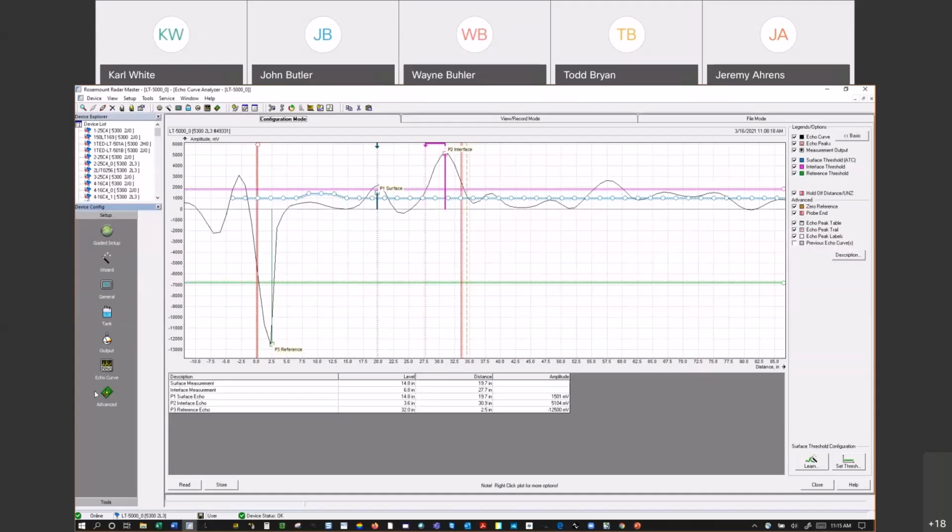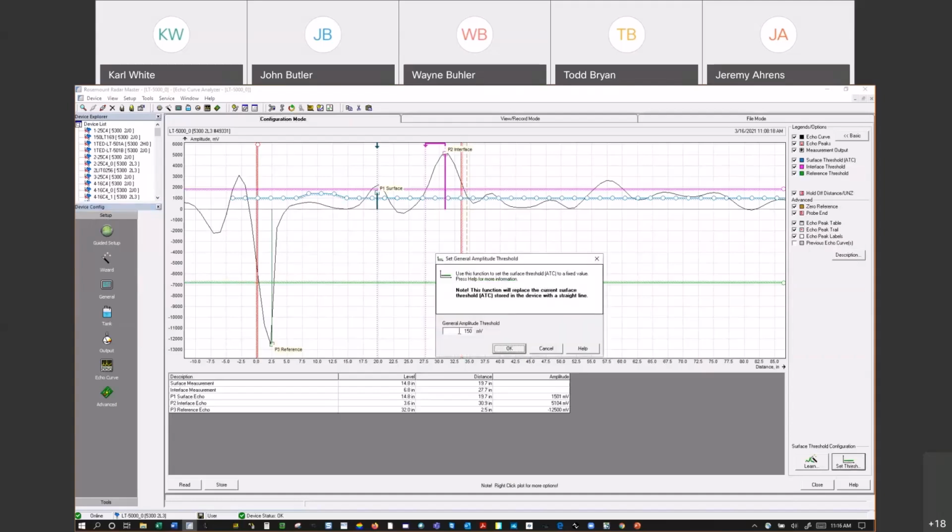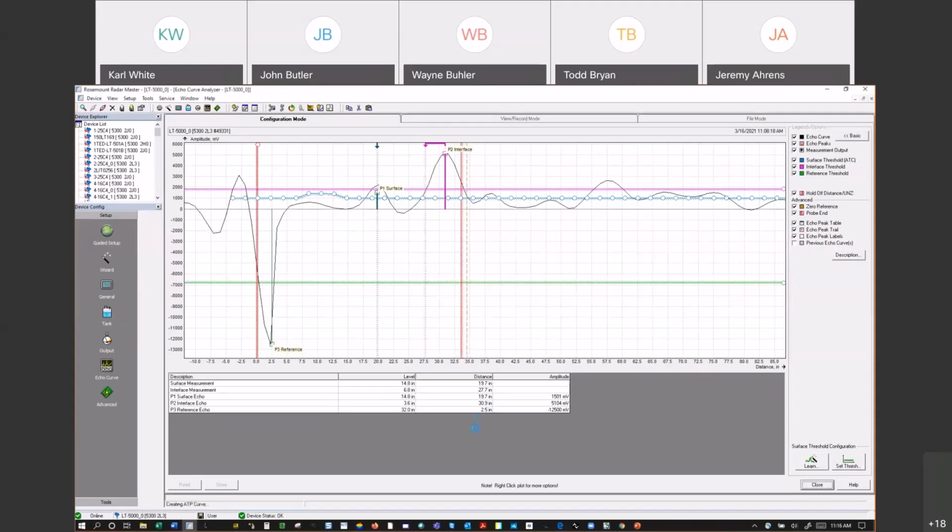So if I'm going on an empty one and I know it's pure hydrocarbon, I'm going to calibrate that just in case I need to use it later. Doesn't hurt anything to run that little cal routine and get it set up. Then if you want to use it later, you just go in and check the box and you're up and running. So I do the calibration generally. If I'm in a place where there's any conceivable way I might have to use it, I'm going to calibrate it when I put it in and the tank's empty.